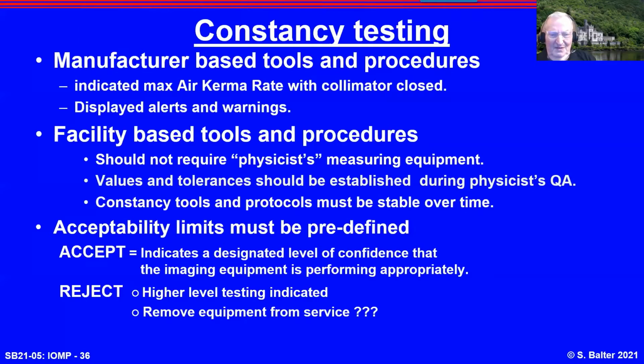One of the common things that was there, almost universally ignored by the physicist, in the days when we were physical beam monitors, they would separately calculate the expected output, and put up a warning if the measured value was too far from the calculated value. You're going to have QA run constancy testing in your institution. You should not rely on the physicist's measurement instrument for everything, but you've got whatever tools you use, establish it.